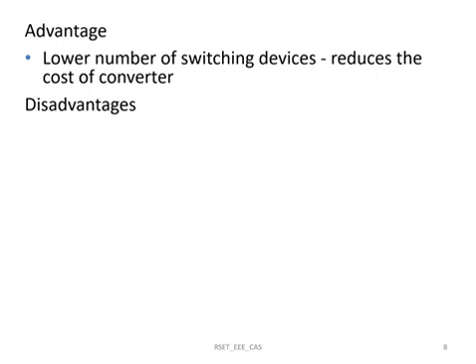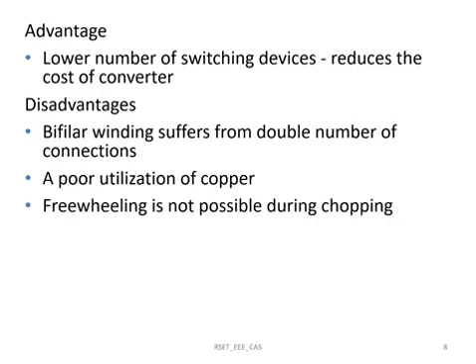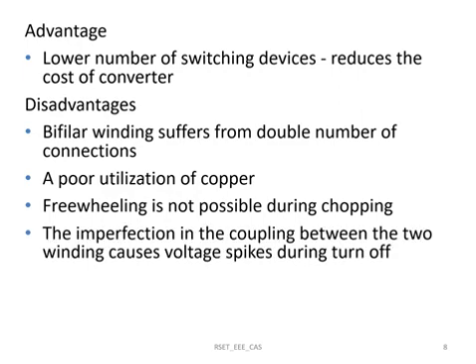For an SR motor with bifilar winding it requires double the number of connections. The main disadvantage is the poor utilization of copper material. Freewheeling is not possible during the chopping operation. If there is an imperfection in the coupling between the two winding sections, it will cause voltage spikes when the switches are turned off. Since more copper is used, the copper loss will be high.